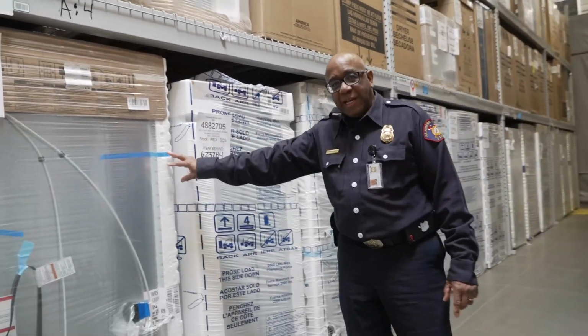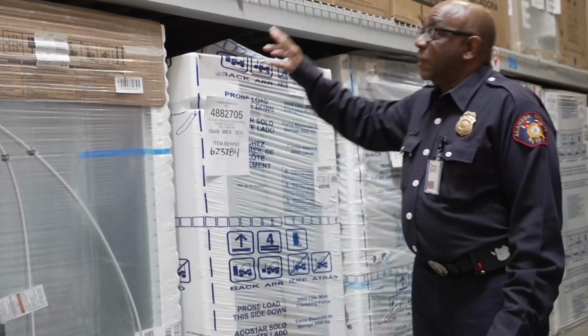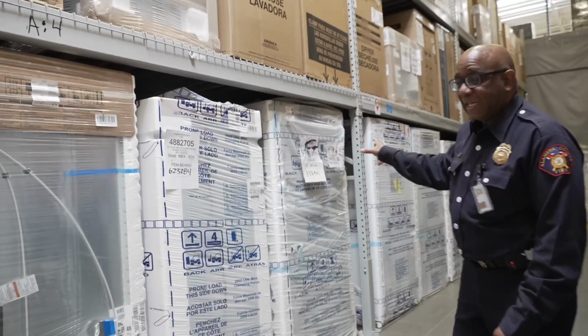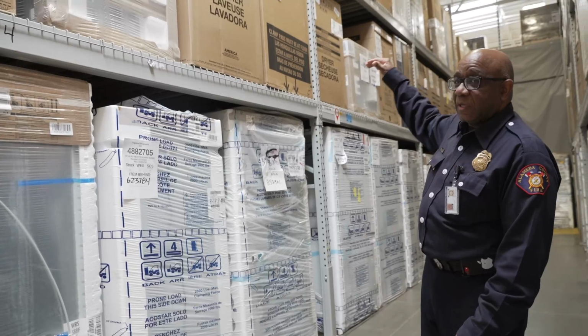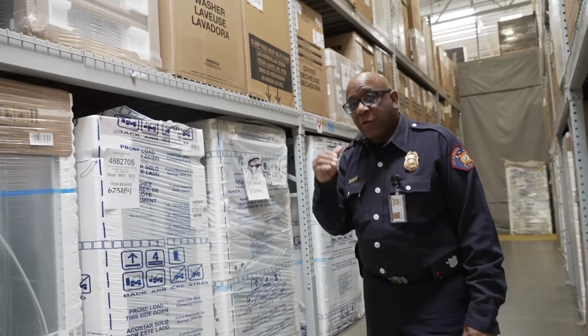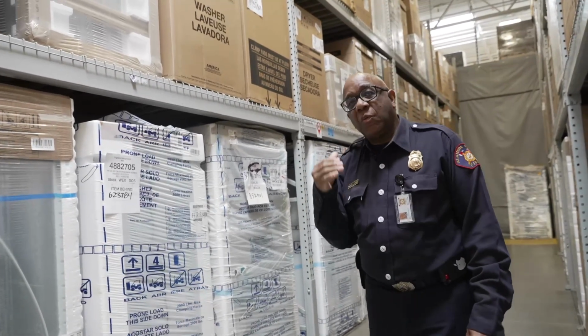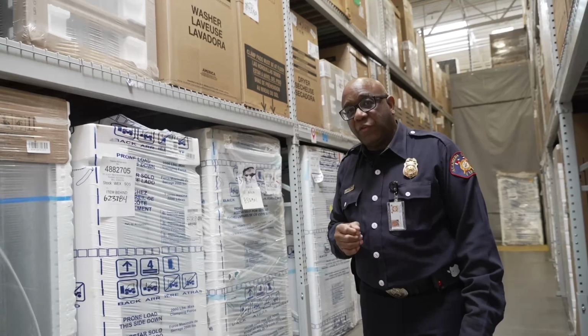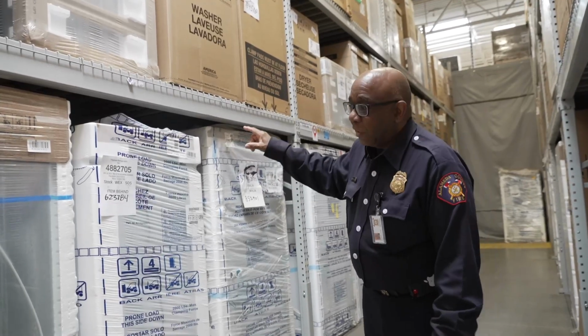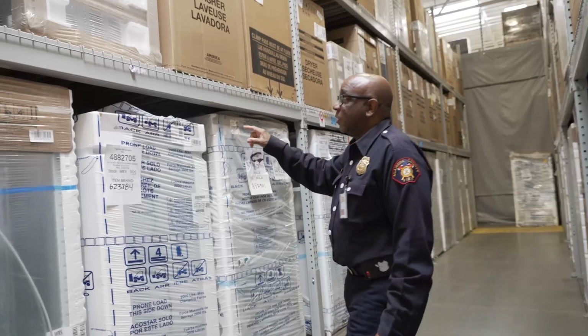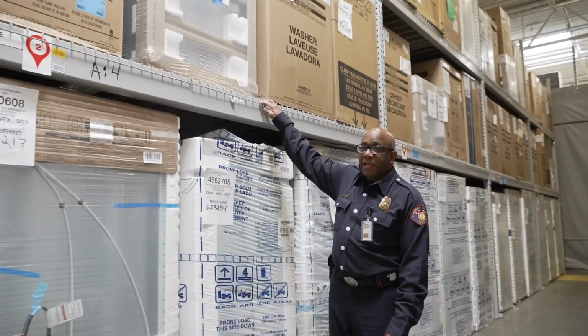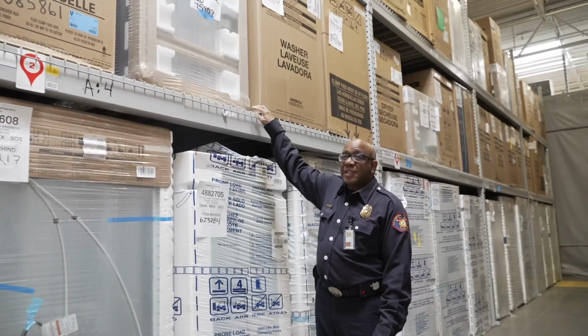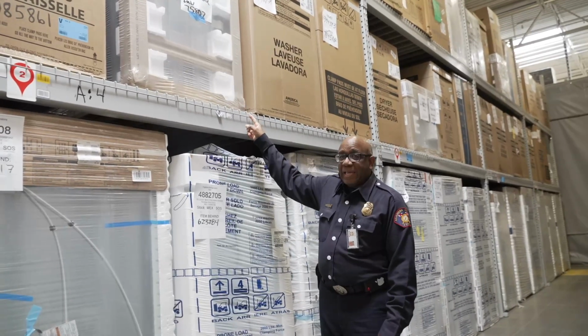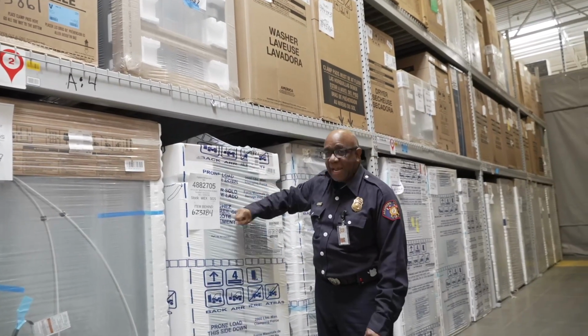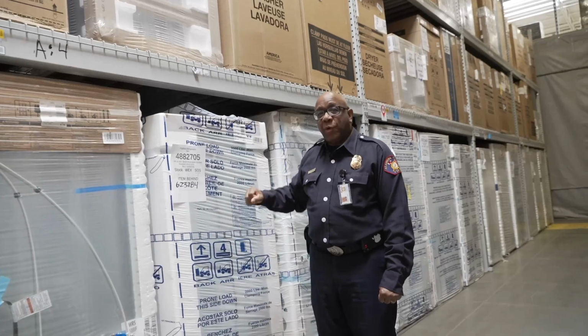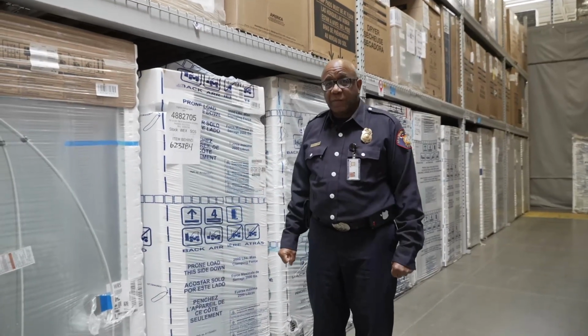We have encapsulated foam, cardboard, tightly packed, dense. So whatever you see that's a violation of that, you want to deal with it while you're with that store. For this style of storage, make sure they have the metal racking rather than the wood slats. With the metal racking, it allows the water to penetrate and get down to this lower layer and put the fire out or control the fire till you can get here.